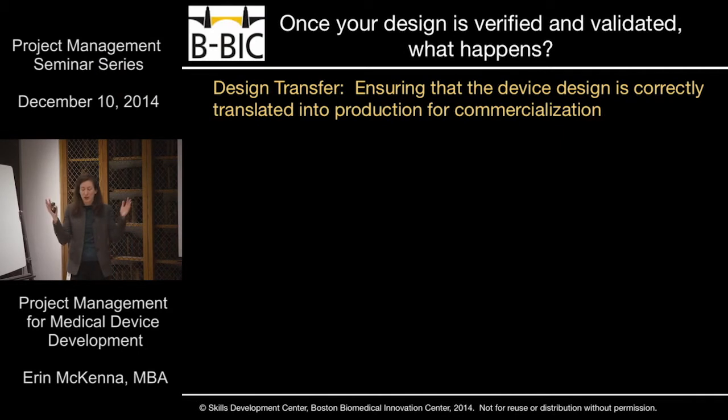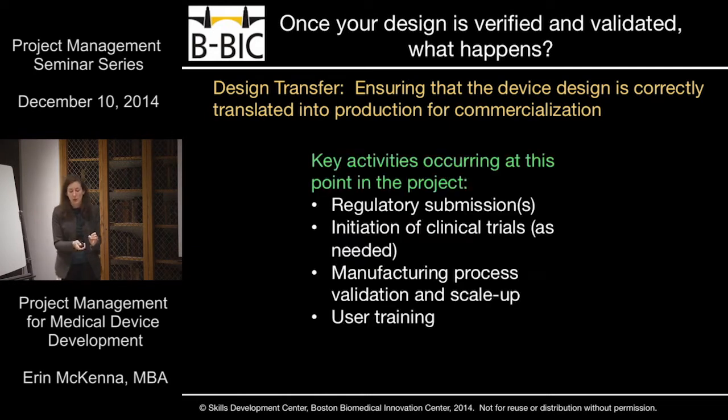Okay, so once you have verified and validated your design, you move into a space described in the regulations called design transfer, where the primary goal is making sure that that design is being translated into a product correctly. So you're focusing on understanding the manufacturing processes that will be used to produce your specifications and making sure that they are producing them effectively. You're definitely bringing in similar kinds of Six Sigma approaches here to make sure that you're getting the most out of that as you can.